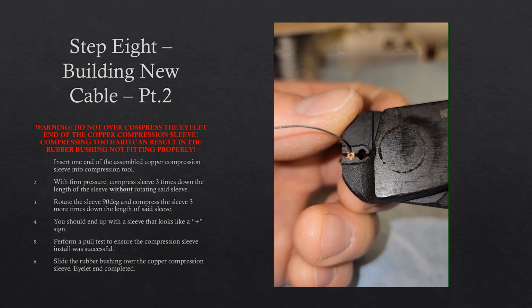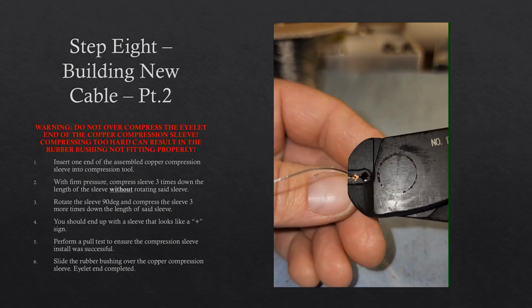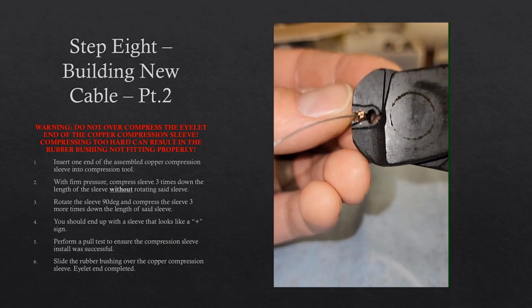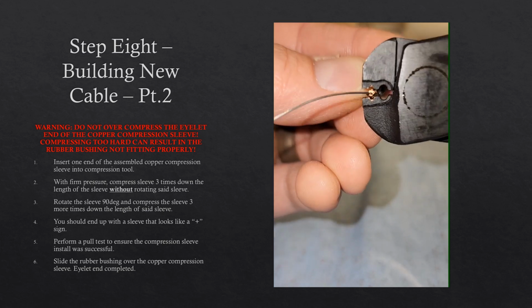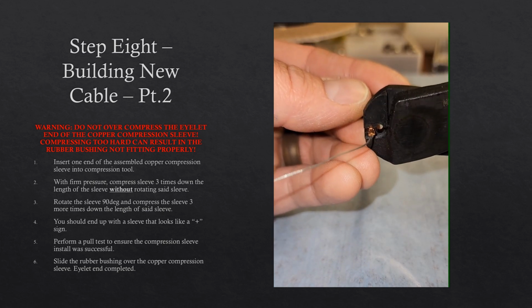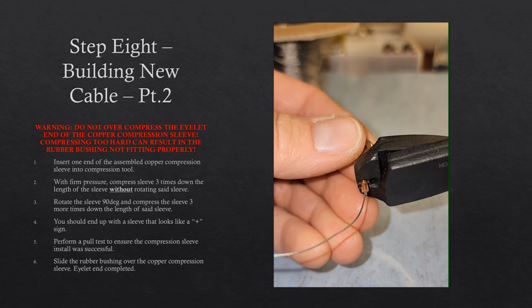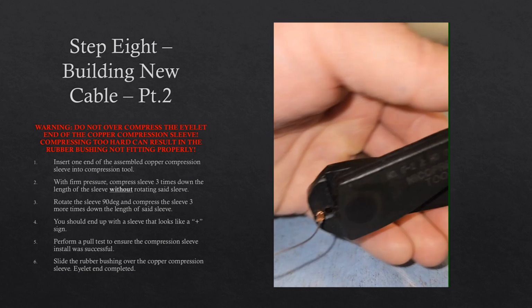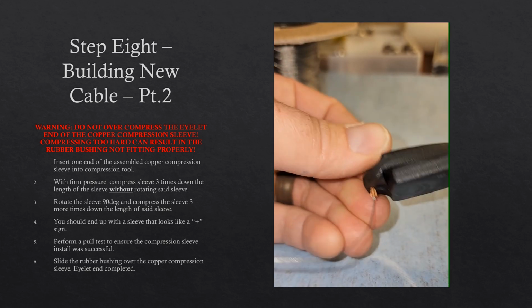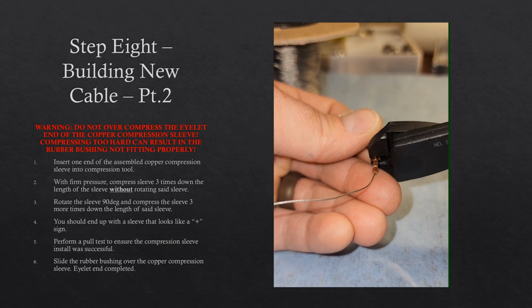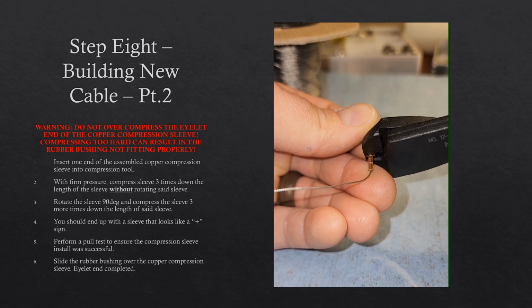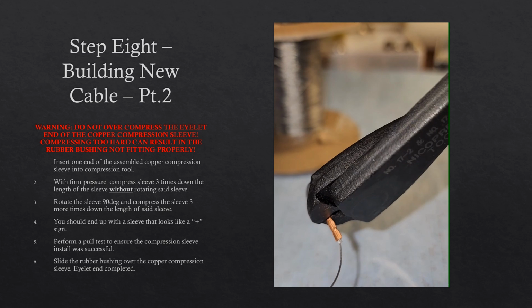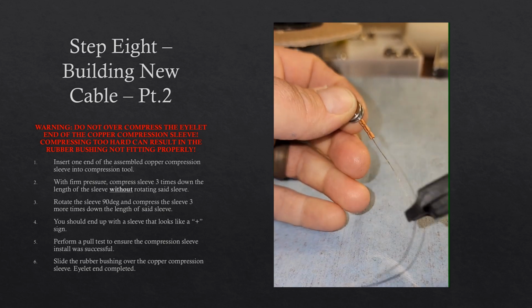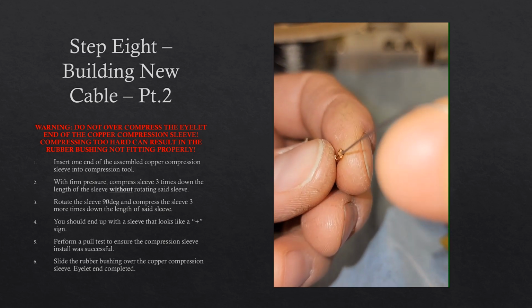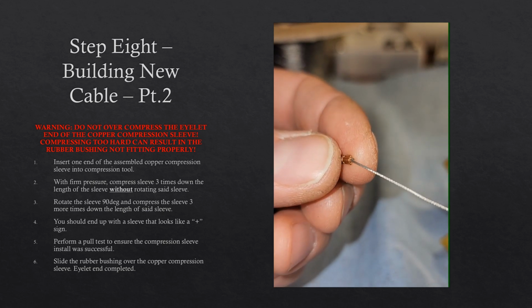So one thing to note is we don't want to over compress this, because if you squish the daylights out of it, that rubber bushing that we need will no longer fit over top of that copper sleeve, or at least it's going to be very difficult to put back on. So make sure you don't squeeze it too hard and over extrude that copper. It is just a soft metal. You want to compress it just enough. Once you get everything compressed, give it a pull test, make sure it's not going to come apart.